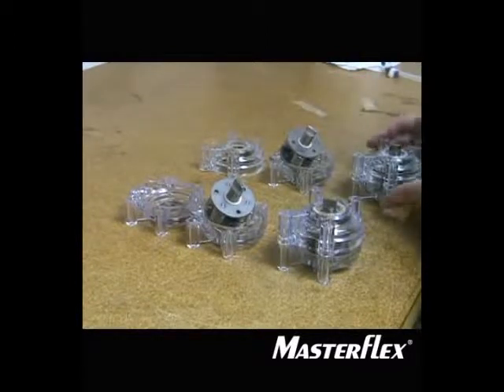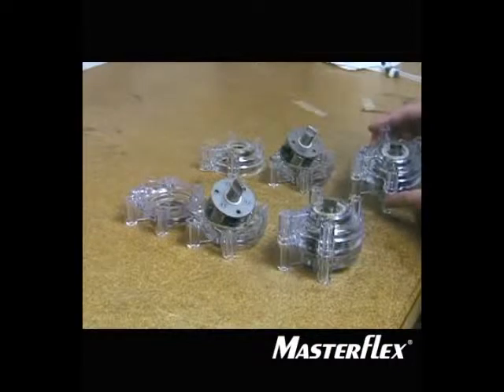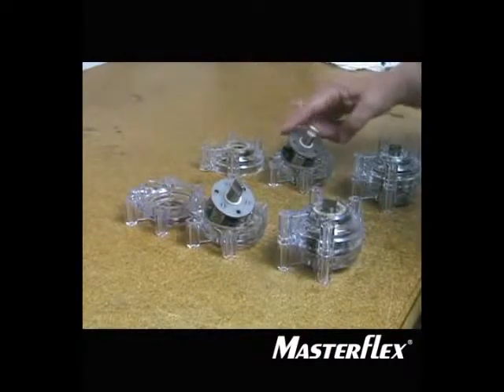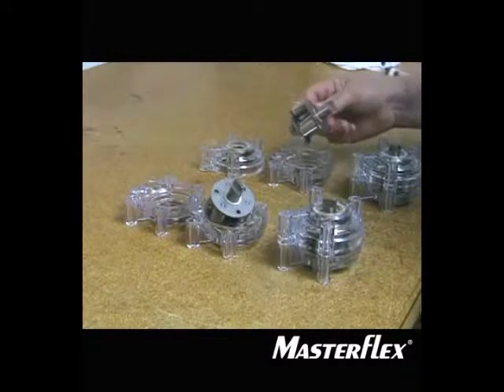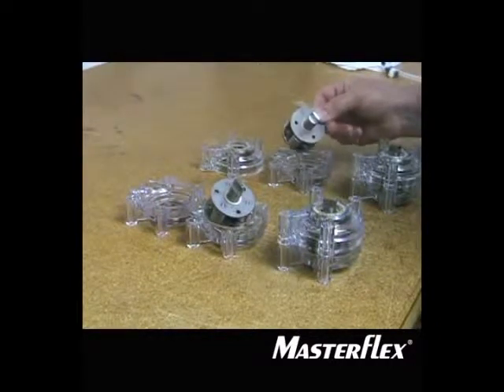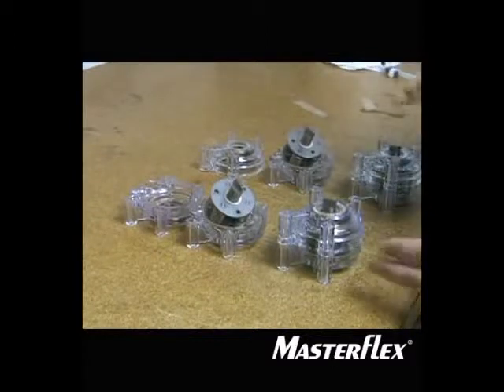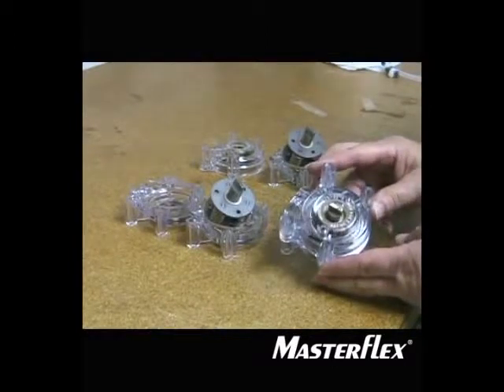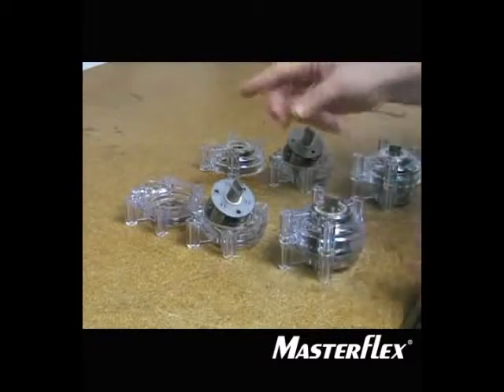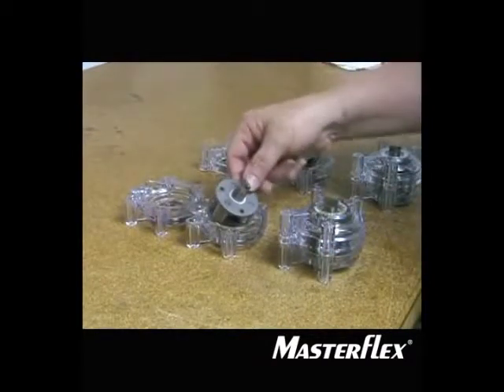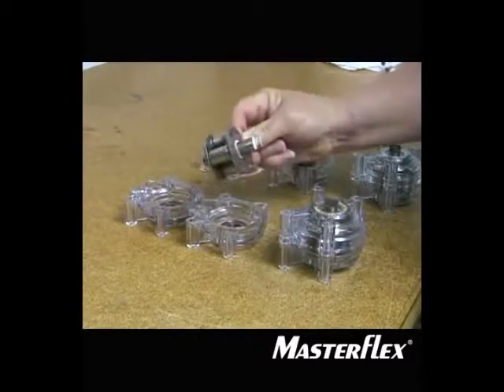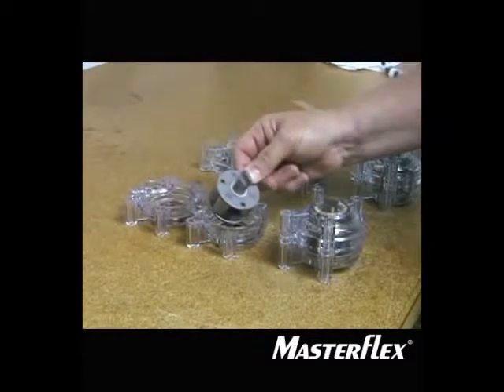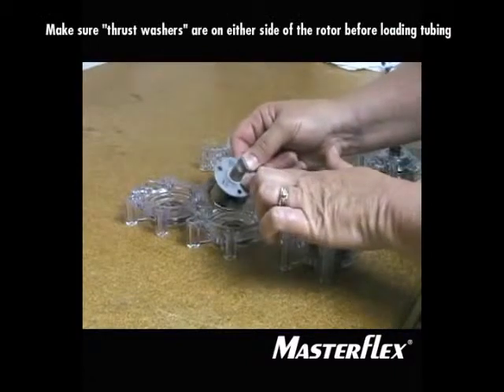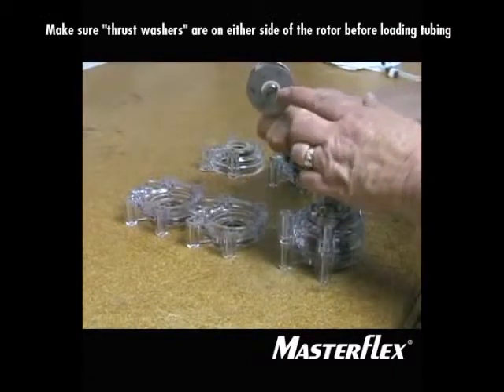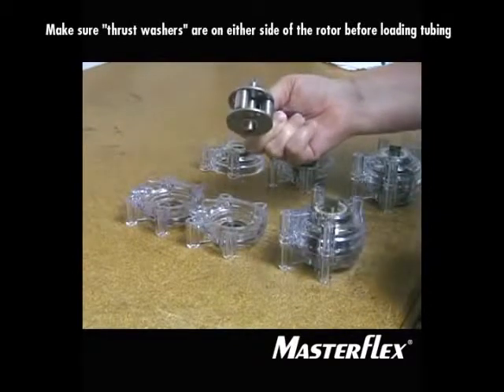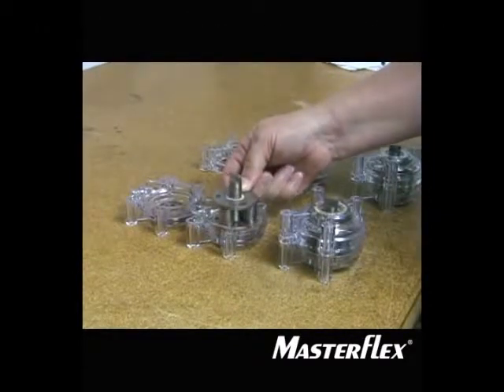This pump head, for example, uses thin wall tubing. It has rollers that slightly extend past the rotor plate. Now this pump head uses thick wall tubing. It has rollers that are located just inside the rotor plate. Notice the thrust washers on each side of the rotor. Check for these before you load your tubing and make sure that both thrust washers are on the rotor.